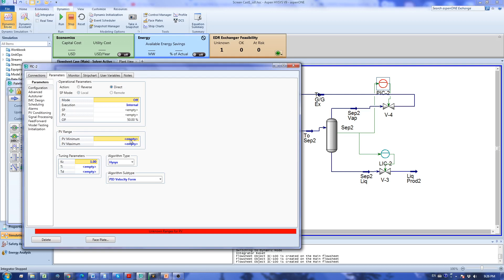For the range for the pressure controller we choose a range that makes sense. Our pressure was about 880 psi so I'm going to choose something like 750 for the minimum and 1000 for the maximum.